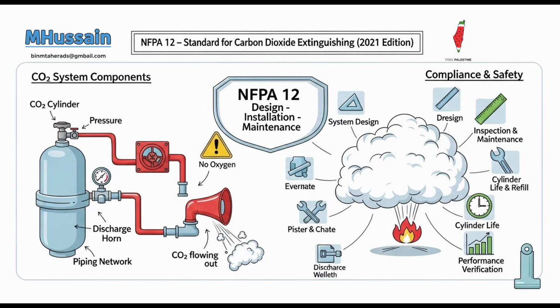Right. The pre-discharge alarms themselves must be highly effective, audible at a minimum of 90 dBA at 10 feet. That's about as loud as a lawnmower or a busy street. Loud. No missing that. And visible throughout the protected space, distinct from general building fire alarms. They must also be located within the enclosure, not just outside. Inside, loud, visible, distinct. Got it. The pre-discharge time delay must be of sufficient duration to allow personnel to evacuate from the remotest points within the space to the nearest exits, considering the fastest possible escape routes. Long enough for everyone to get out. And here's where it gets really interesting and a bit provocative, considering the emphasis on delays.